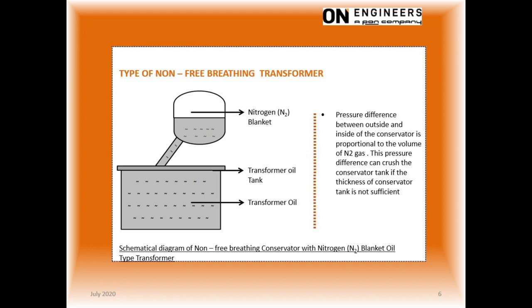There will be a pressure difference between the outside air and the headspace inside the conservator tank. As the oil volume contracts due to decreased loading, the outside air will have a larger pressure than the inside headspace. This pressure difference can crush the conservator tank. For a larger transformer, this non-breathing design will not be suitable.